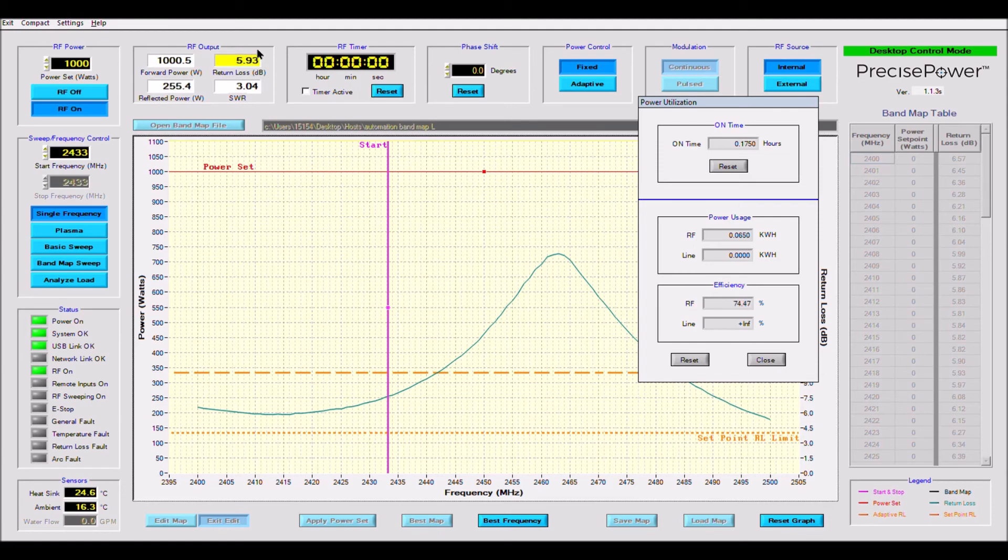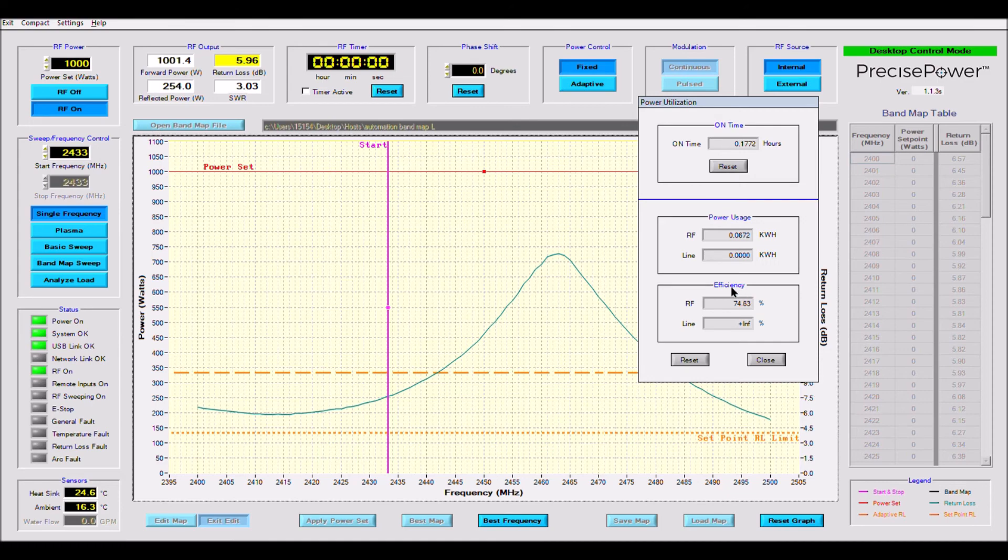The power utilization screen also shows our efficiency drop from 95% to roughly 75%. If the return loss falls too low, the box will be illuminated red and the system will eventually protect itself and fault, preventing damage.